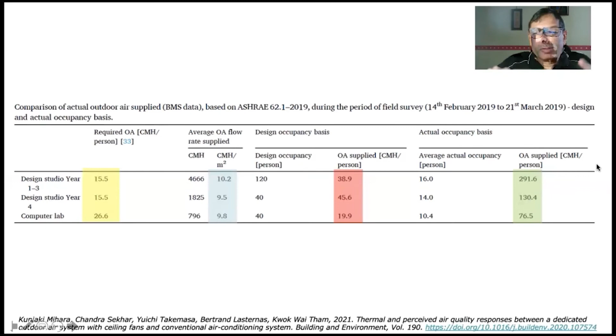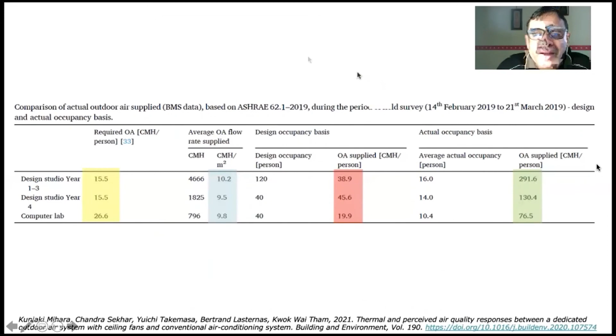The reason I'm showing you these numbers is to say what they mean in terms of absolute percentage energy savings. To do that, from the measured data we need to estimate, let's say, the cooling load demand in these spaces. Here it is for the average normalized cooling coil loads, measured heading towards energy conservation or energy efficiency sort of information.